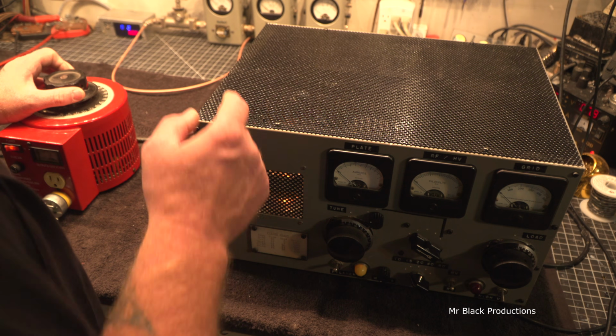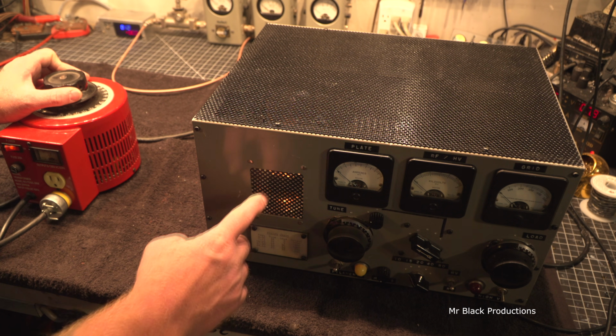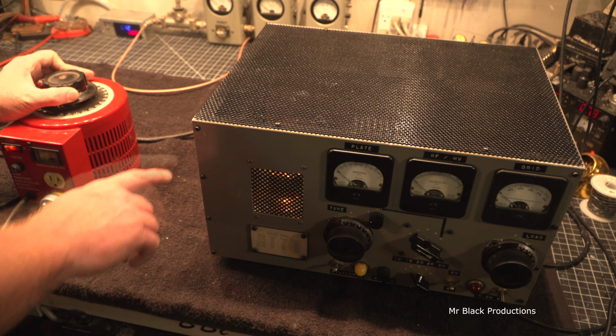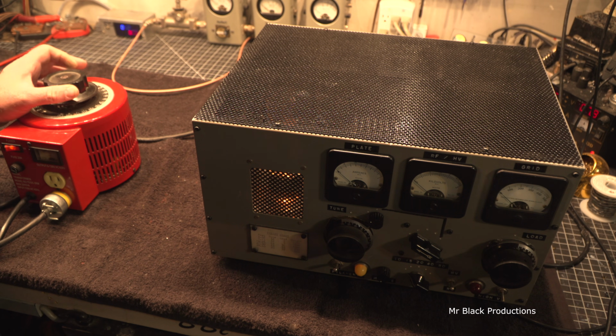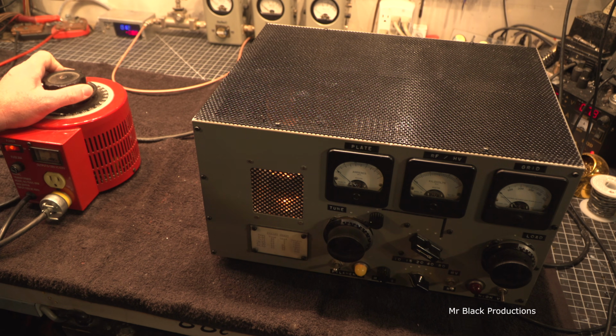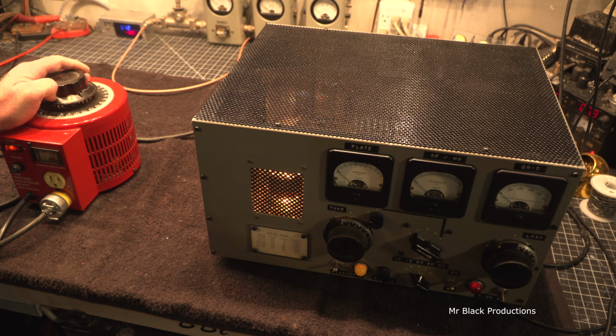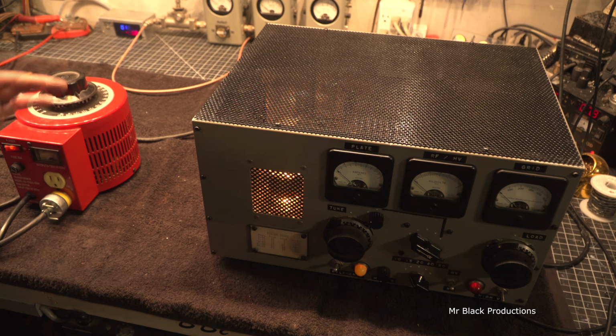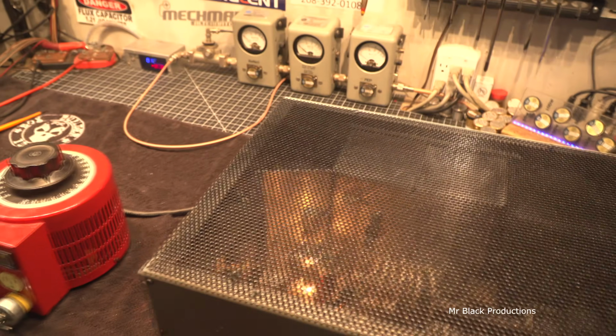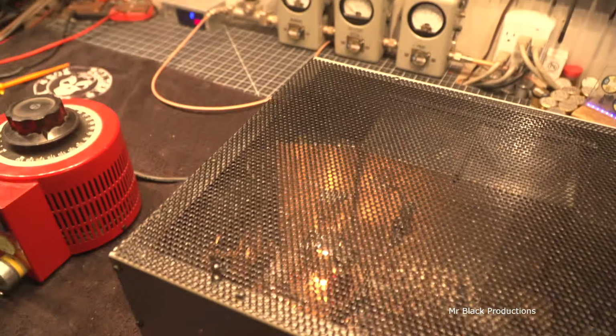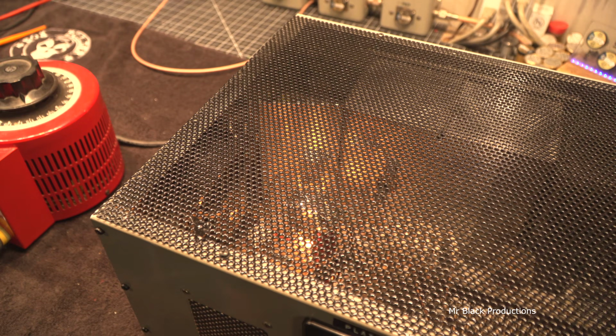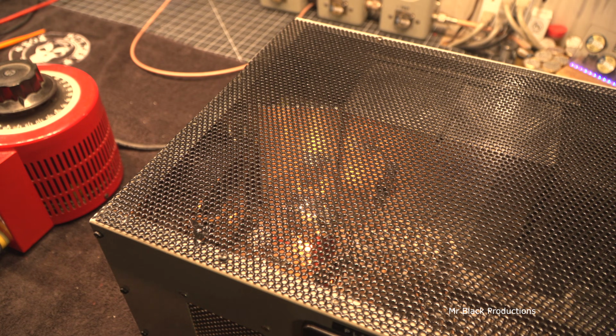Now we're going to start looking at the tubes. The tubes are starting to light up. You can see it through this window. Our fan's starting to turn, and we're all the way down at about 75 volts. We're going to very slowly turn this on. 110 volts. Now we're looking at our tubes, and we're looking to see if they light up. Now you don't want to do this test for very long.